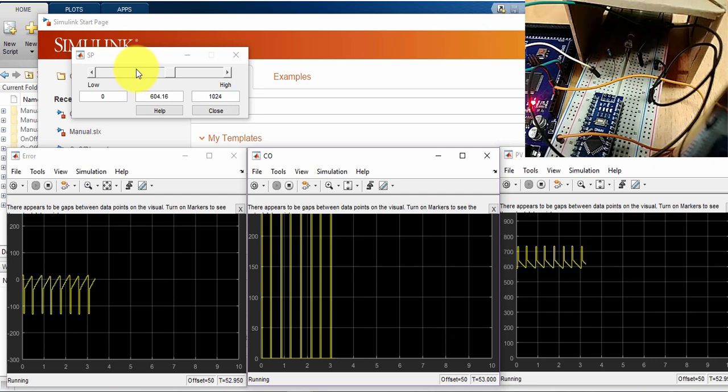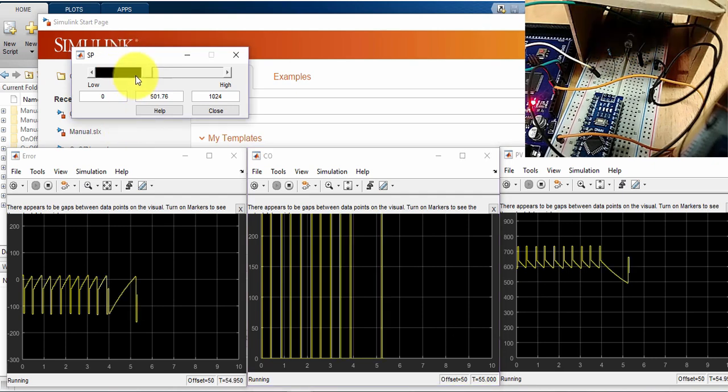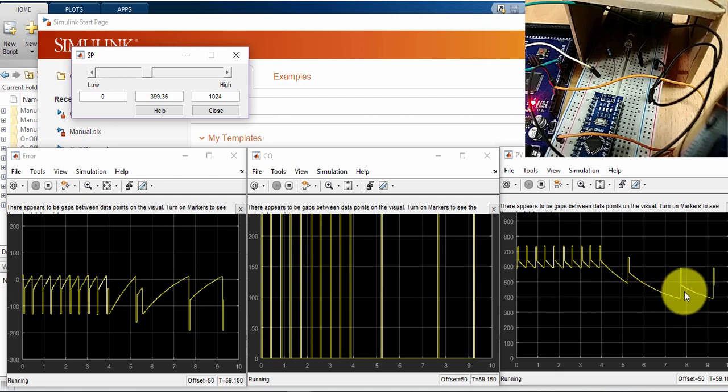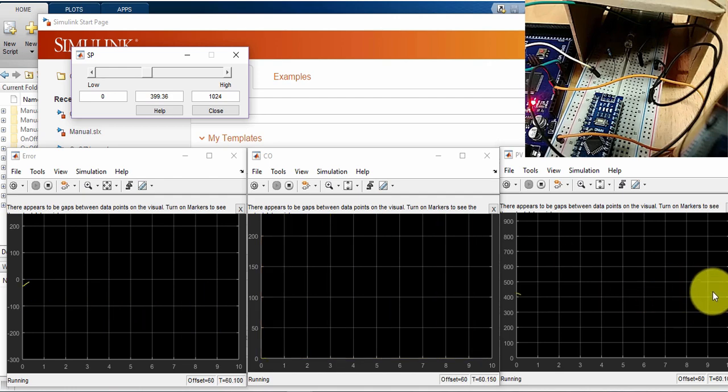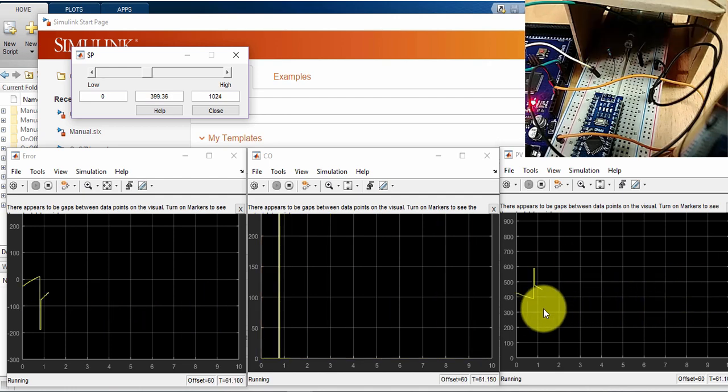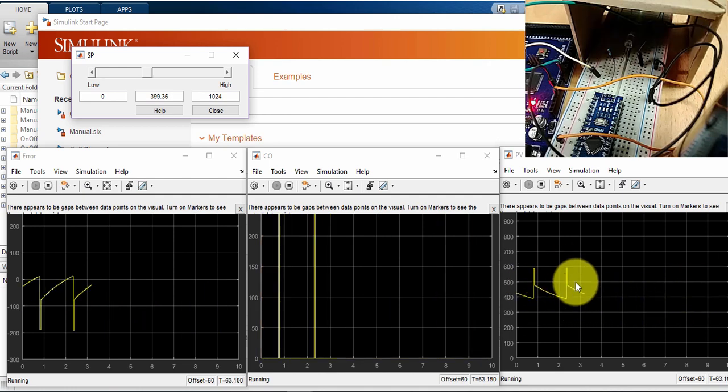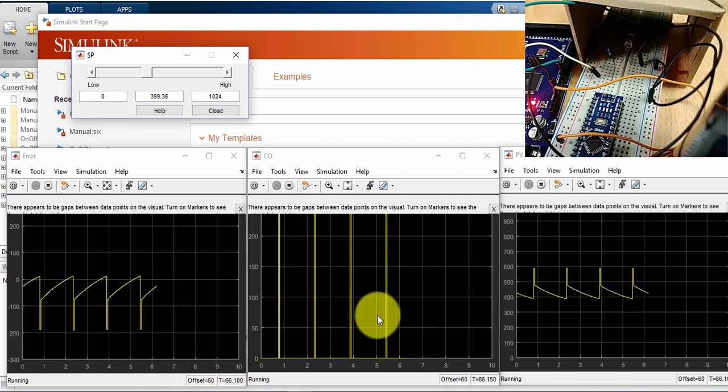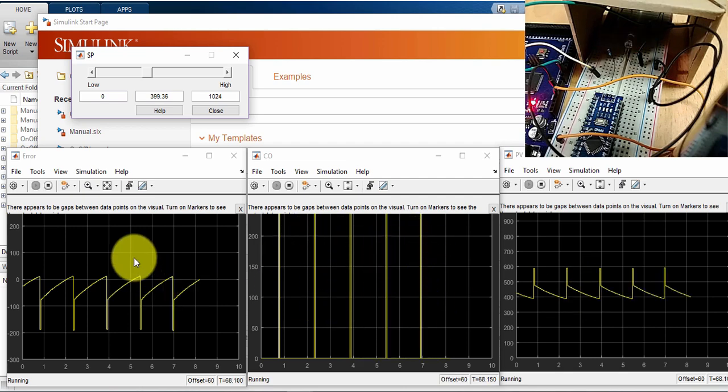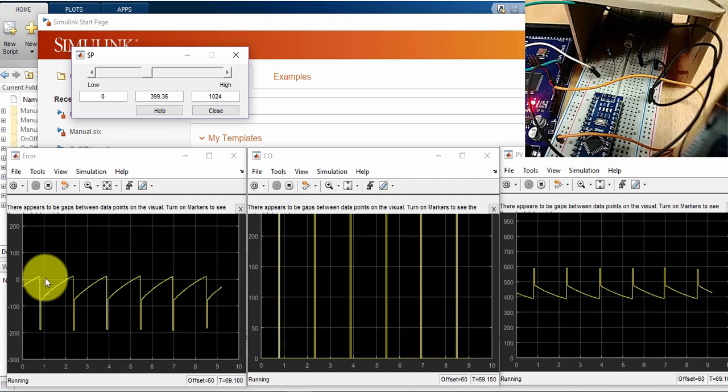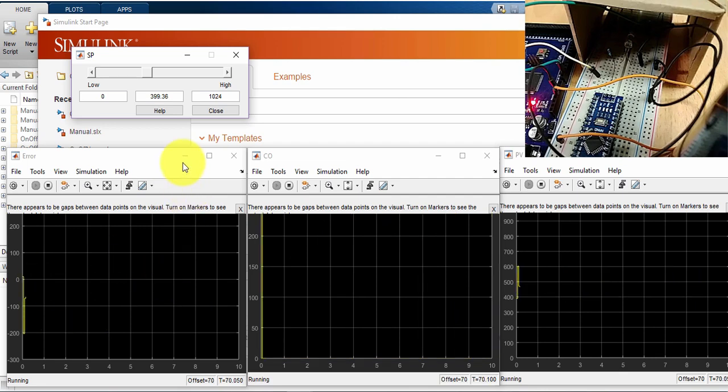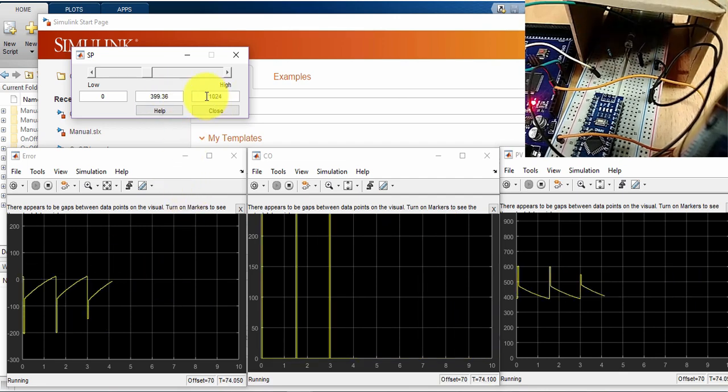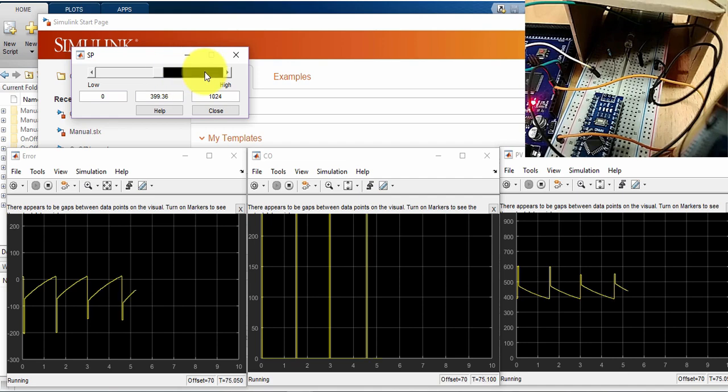So I'll change the set point to 400, and you will notice now, the PV is hovering around the set point, I'm having less frequency on the on-off, and you can see the error, and you can see the light is actually flashing slowly.